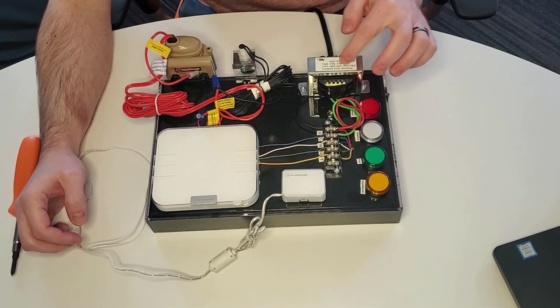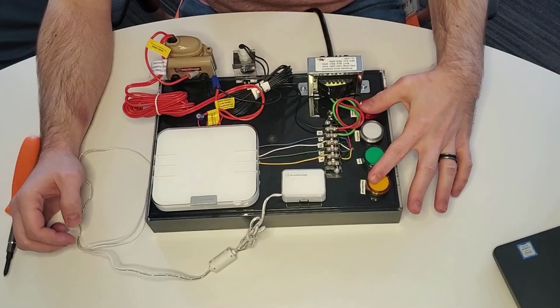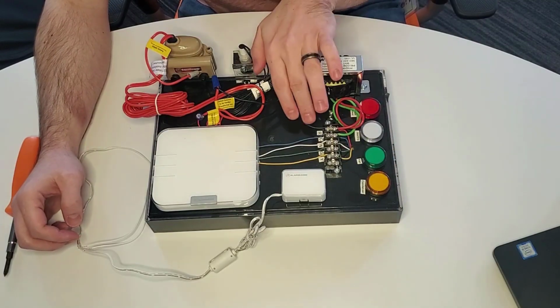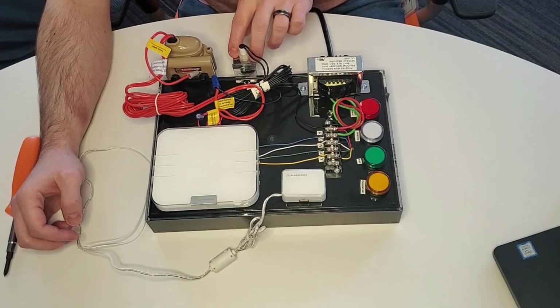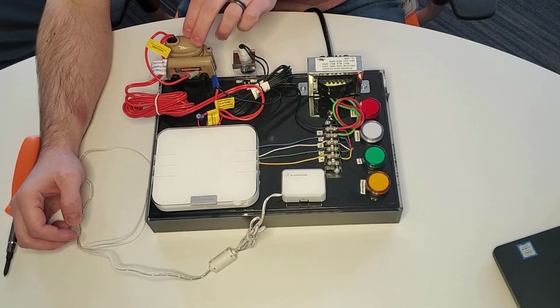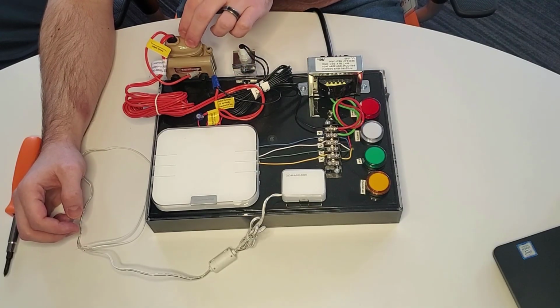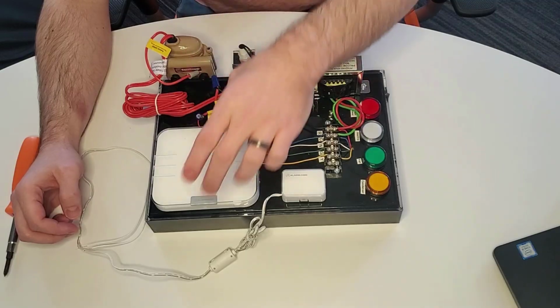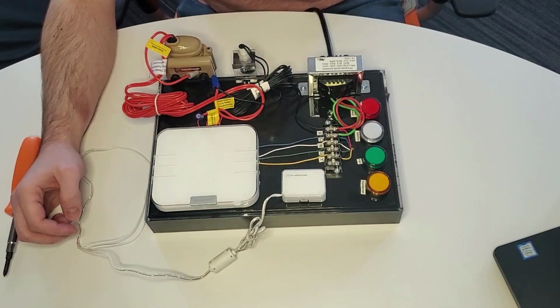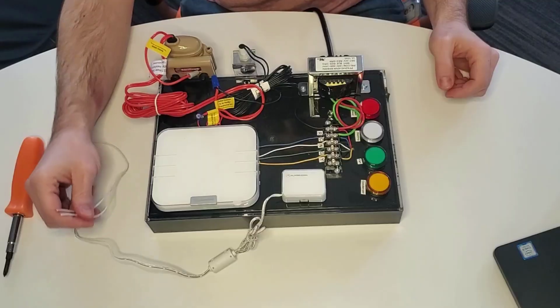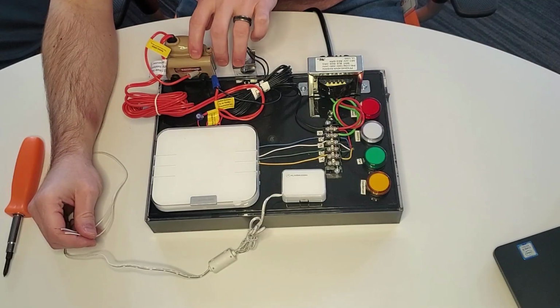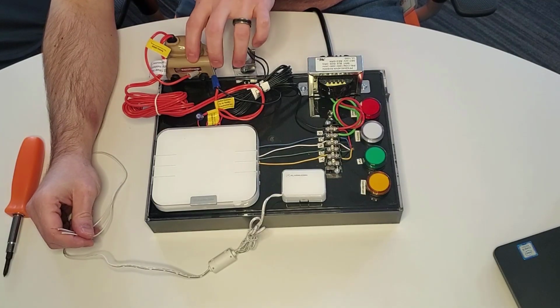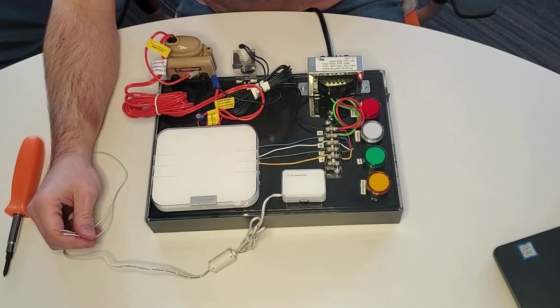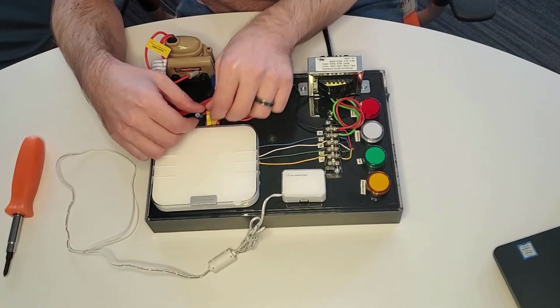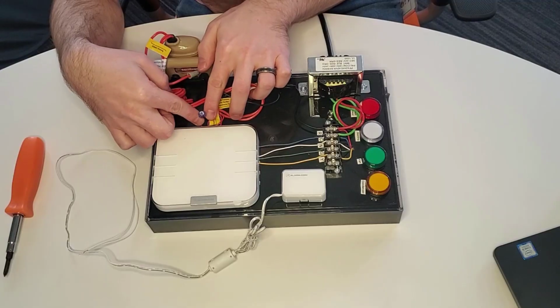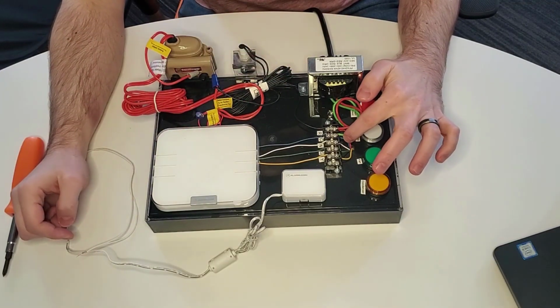As of now, power leaves the transformer and goes to our control board, leaves the control board and enters float switch 1, leaves float switch 1 and enters float switch 2, leaves float switch 2 and enters the thermostat. For the dry contact sensor to monitor the float switches, it needs to monitor the voltage at the last float switch in series and common.